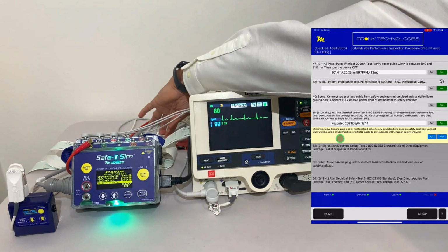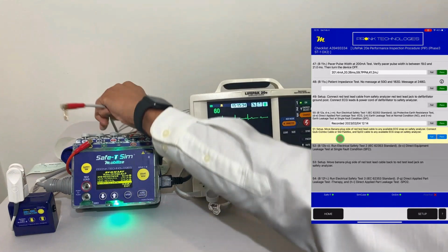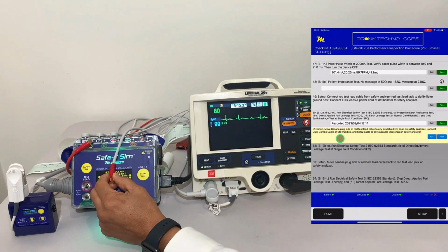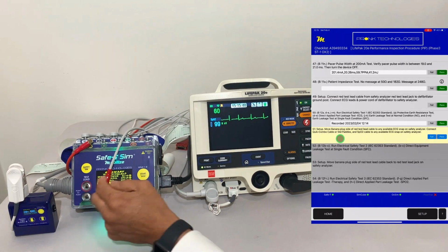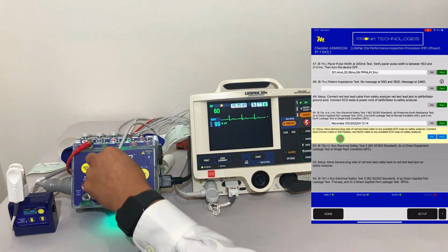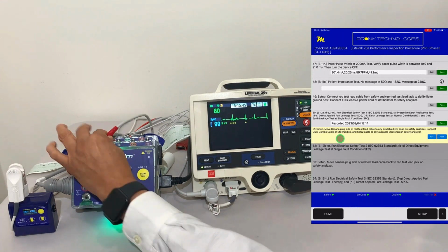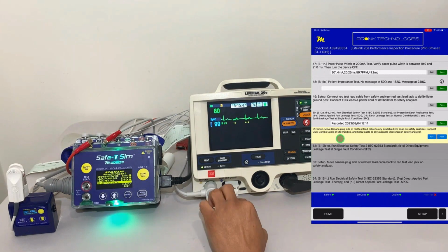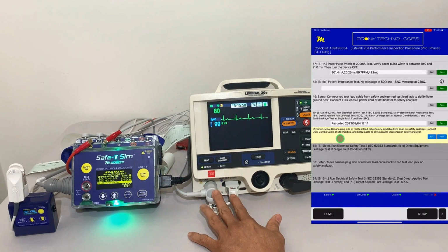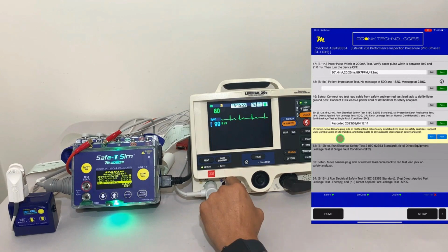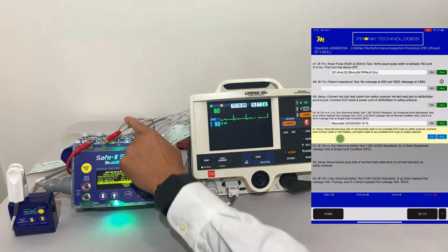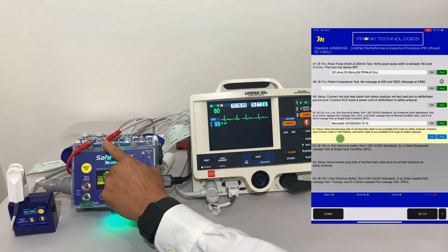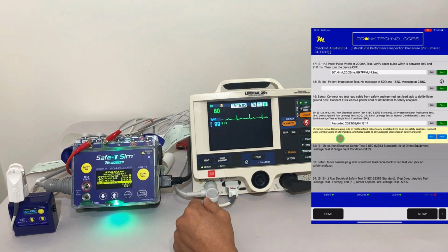We also are going to connect the SPO2 test lead cable. It's an adapter available from the manufacturer that allows me to connect my SPO2 over to my safety analyzer so we can do a lead leakage test on this applied part. Anything that can come in touch with the patient is considered an applied part. We need to do a safety leakage test on it as well. So we've connected the SPO2 adapter cable from the defib over to this banana plug connector that we can now connect over to the safety analyzer. So that's the second thing we've done.